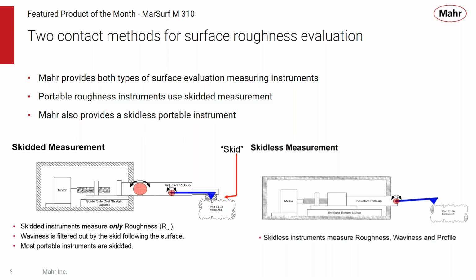Well, a skidded measuring system uses a probe that has a reference surface built into the probe itself, the skid itself. So as that probe is moved over the part by a drive, the skid runs over the part, a very precise measuring tip or stylus passes through that skid to get the actual roughness measurement. So these types of skidded measuring systems measure only roughness, an R parameter. Because the skid is floating over the surface, waviness is filtered out by that skid because it's following the total surface. So most portable measuring instruments are skidded based.